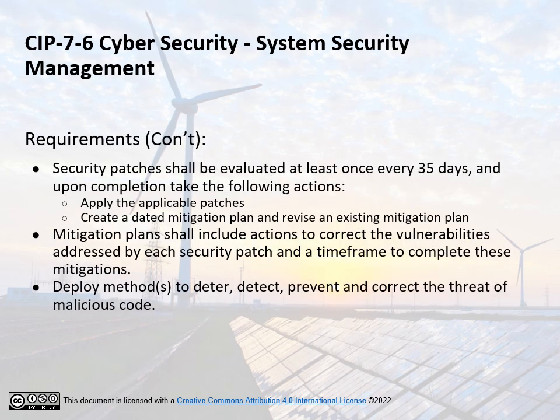CIP-007-6 System Security Management. Requirements continued. Security patches shall be evaluated at least once every 35 days, and upon completion take one of the following actions: apply the applicable patches, create a dated mitigation plan, or revise an existing mitigation plan.